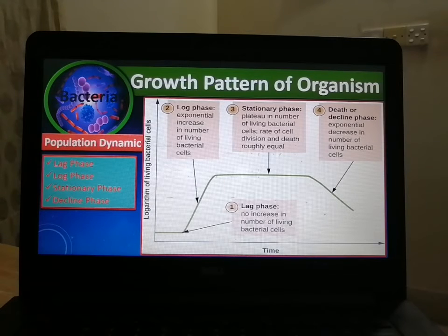And in this area, if the system has heavy organics, or if the system is contaminated with some external nutrient, or has high TDS or high turbidity or other things, they are allowed to grow. But in most systems, if it is fouled, they stay here as a stationary phase. An equal number of bacteria grow and an equal number die. If the system stays here, then it is already a very fouled system.